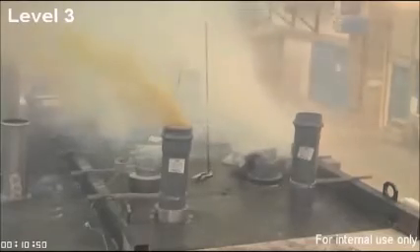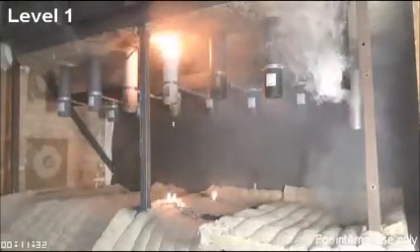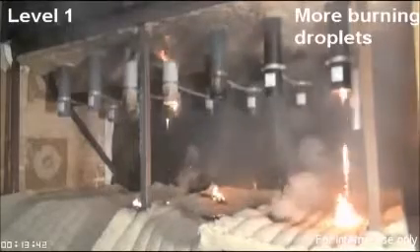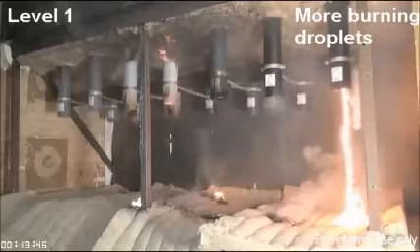The smoke starts to decrease; however, the plastic pipes are still melting and deforming. Just over eleven minutes have passed, as the burning droplets from several pipes create fires below. The heat-activated fire seals still haven't worked towards the lower deck. At this point, one of the PP pipes has nearly burnt away close to the deck and is about to fall down.